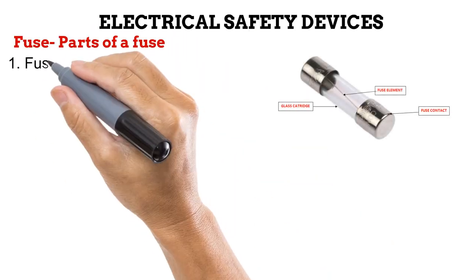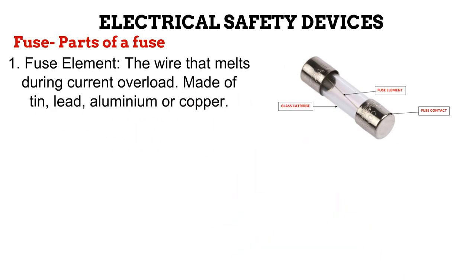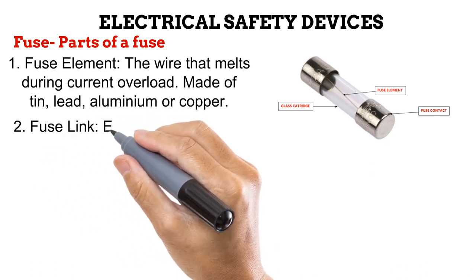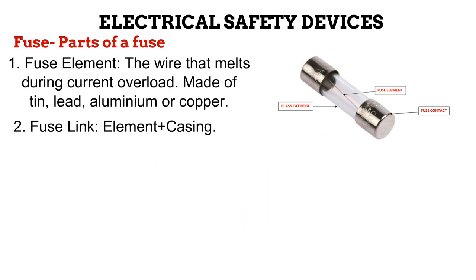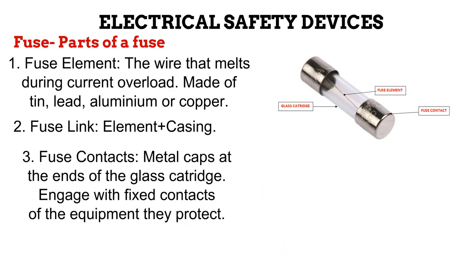Let us look at the parts of a fuse. First is the fuse element — the wire that melts during a surge or current overload, and can be made of tin, lead, aluminium, or copper. Next is the fuse link, which is the fuse element plus its casing. Most commonly, a glass cartridge serves as the casing. However, there are open fuse links, which have no casing. Fuses with a casing are better than open fuse links because open fuse links tend to produce an open spark when they melt. Lastly, the fuse contacts are the metal caps at each end of the glass cartridge that engage with the fixed contacts on the equipment they protect. Even though the fuse gets destroyed performing its protective function, it is far less expensive to replace a fuse than to replace damaged equipment.